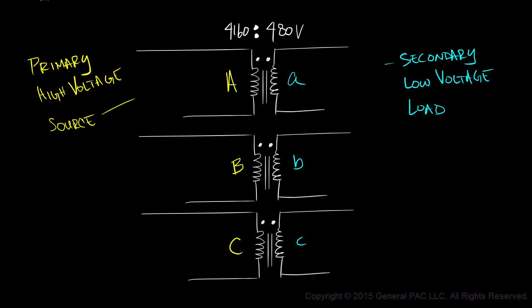Since we're illustrating a delta Y transformer connection, let's start by connecting our secondary windings in Y. We're going to connect winding A, winding B and winding C together. And for the sake of simplicity, we're going to ground the neutral wire. This is a Y grounded transformer connection.